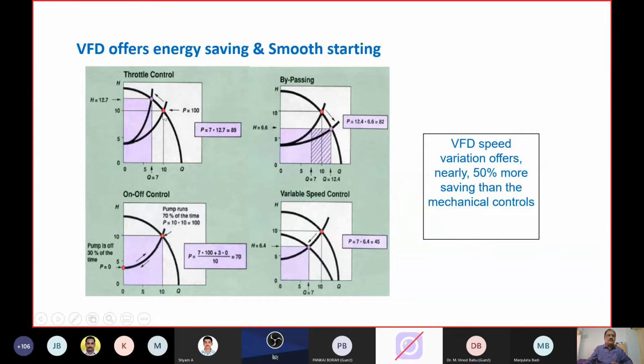When you throttle, 10 by 10 is the normal dimension, the original engineering design of the pump. This is 10 on the flow, which is Q. H is the head, which is in meters. So if you put 10 by 10 as the original design curve for the pump, you are on this curve. And this is the design optimum load, where 100% power output is available from the motor and pump put together.